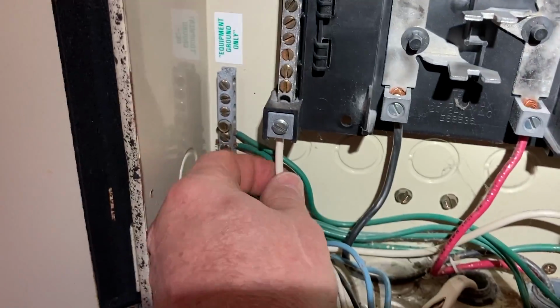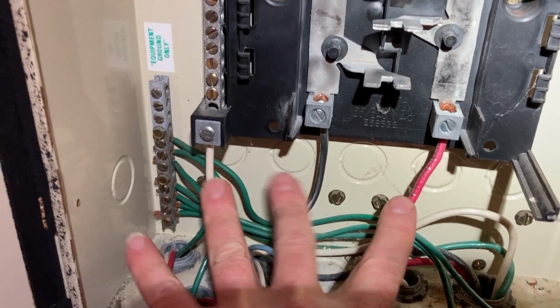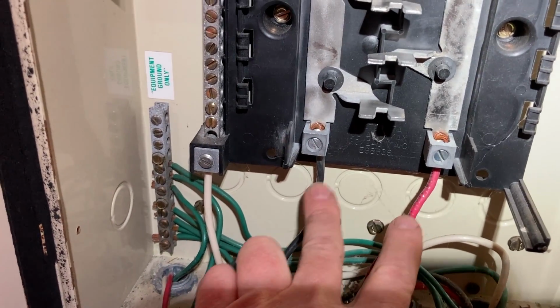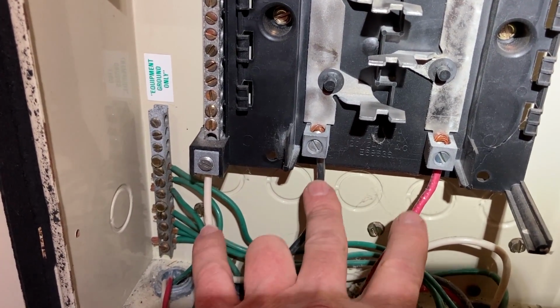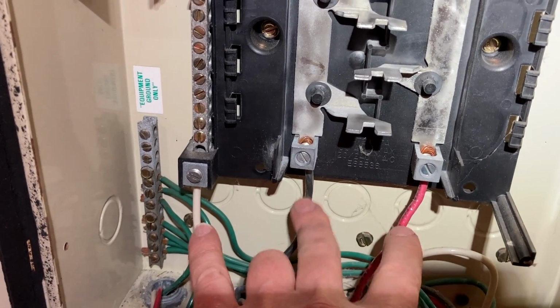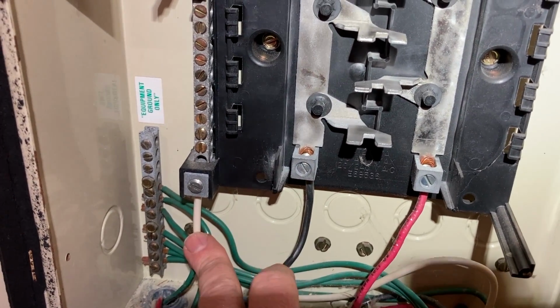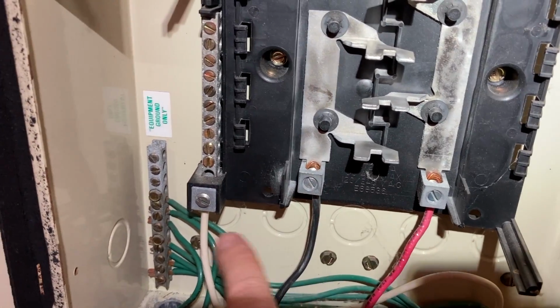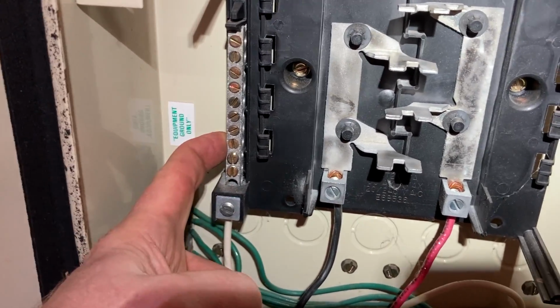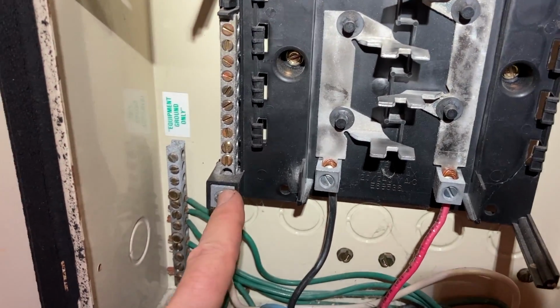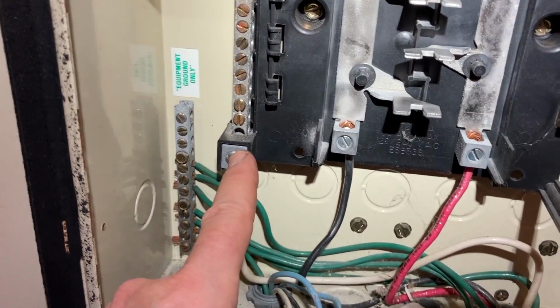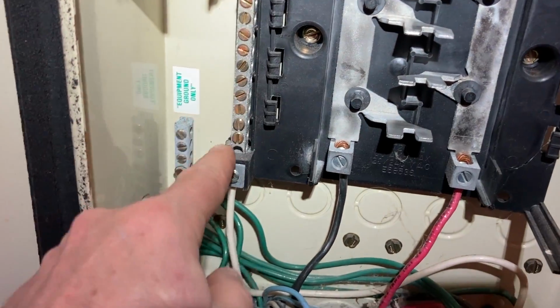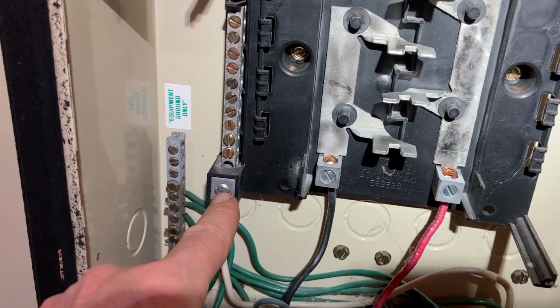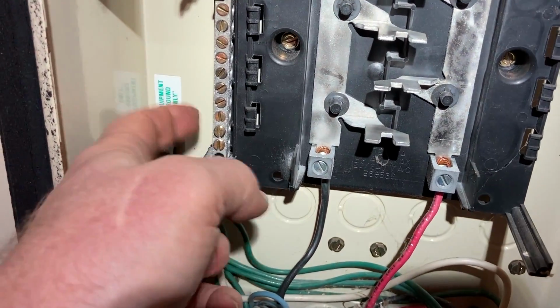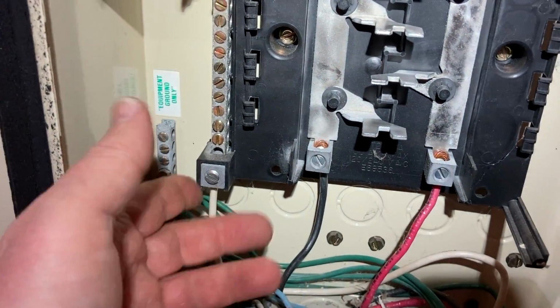And surprisingly, this neutral feeder—these are the three feeders, the two split phase legs of the 240 and then the neutral—was going into one of these terminals on the side instead of into the bus screw where it should go, and I'm not sure why they put it in here. So I moved it, and then I tested for continuity in case it was broken for some reason, but it seems fine.